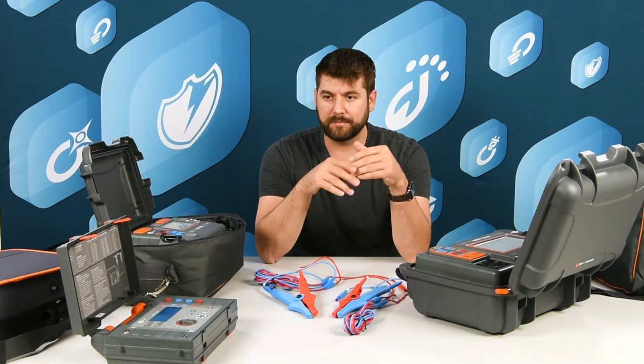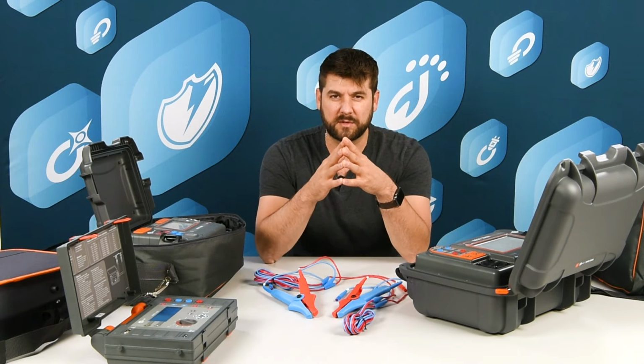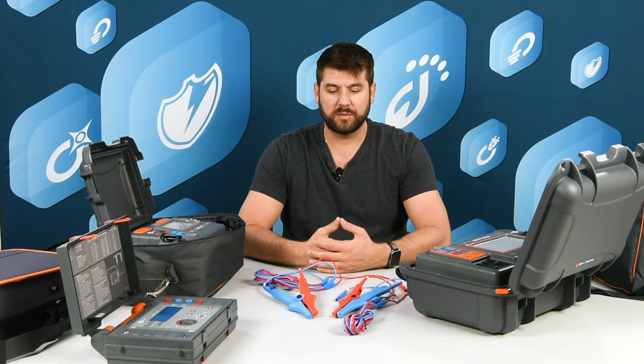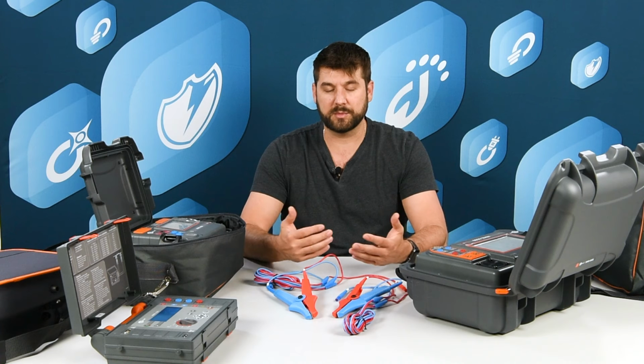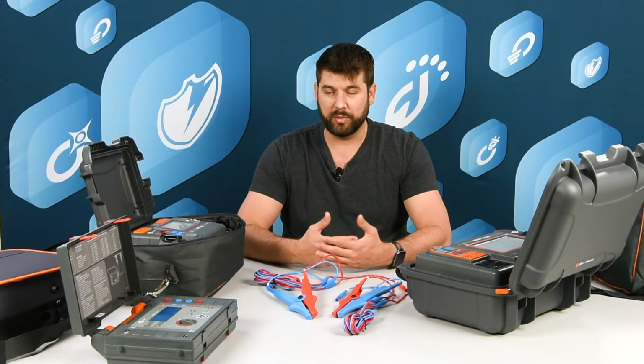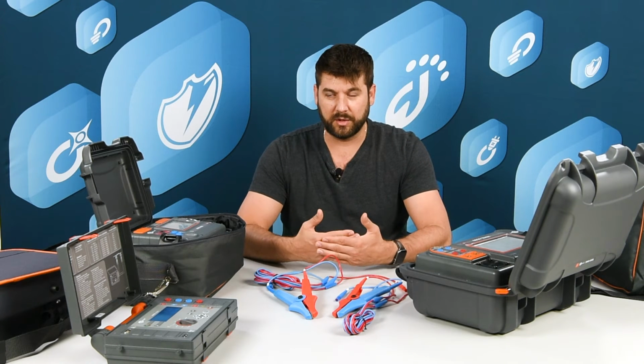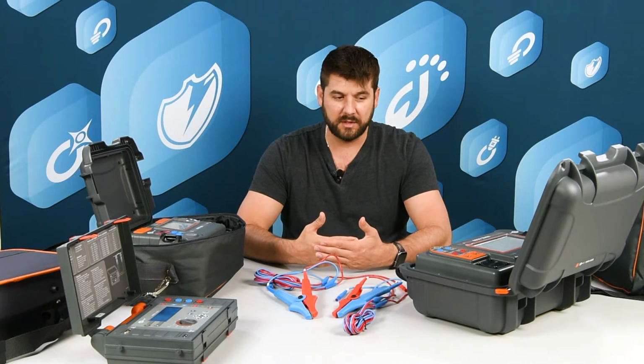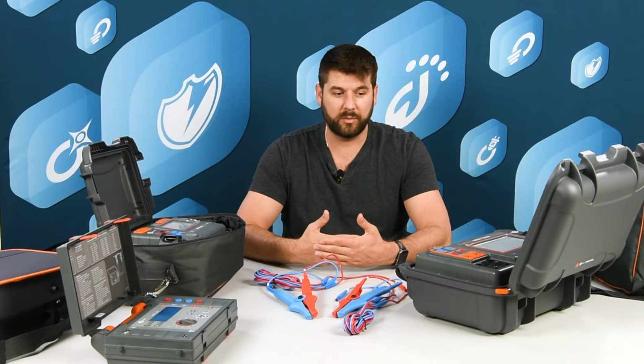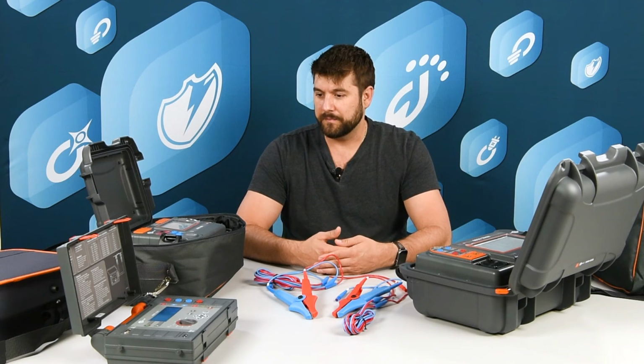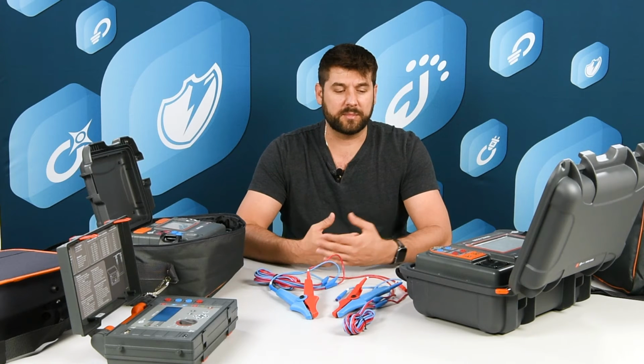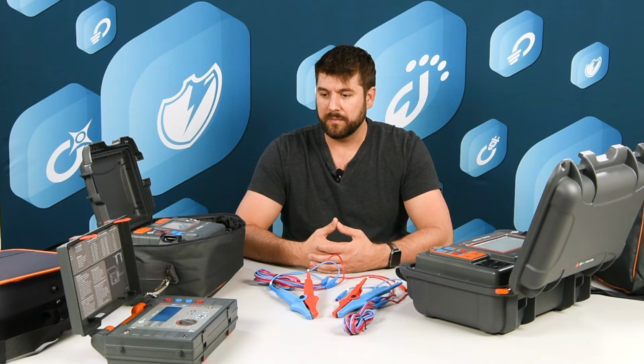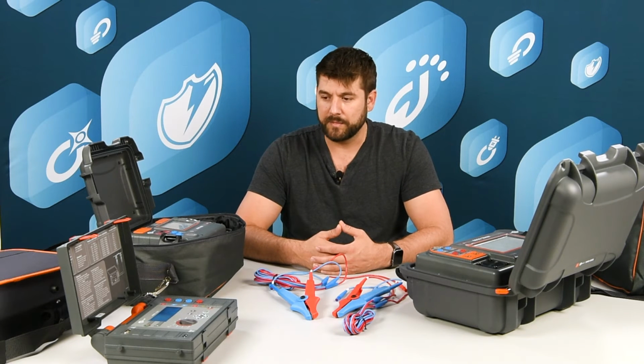So it's very elementary and fairly simple, and really the most important concept in electrical power is that the conductors have adequately low resistance so that they can carry a lot of current without getting hot. And depending on which type of device you're testing, you can choose the microohmmeter that's going to give you the measurement results in the range where you need.